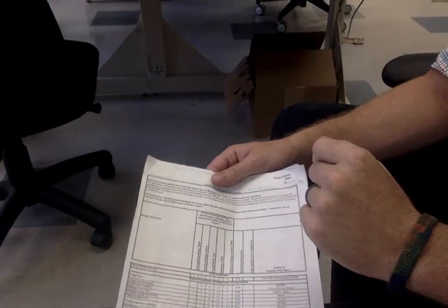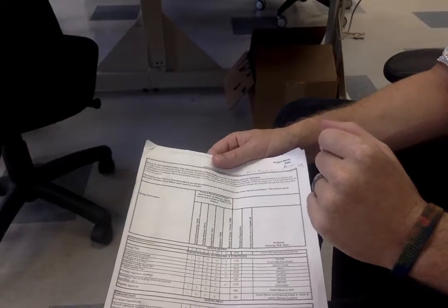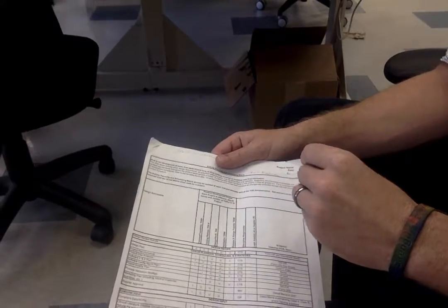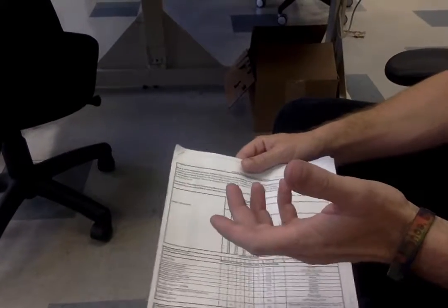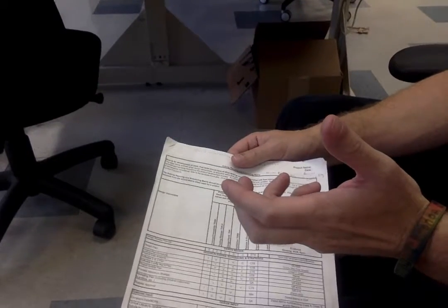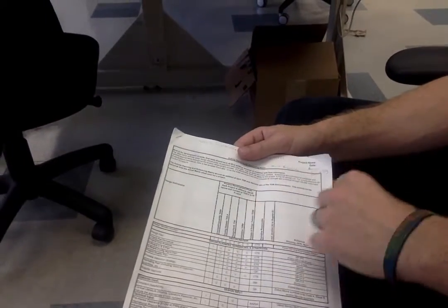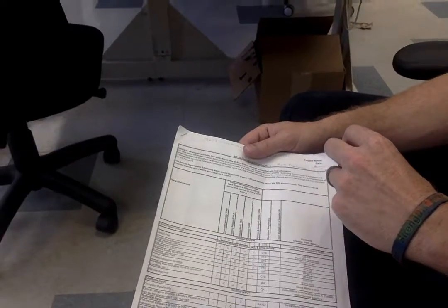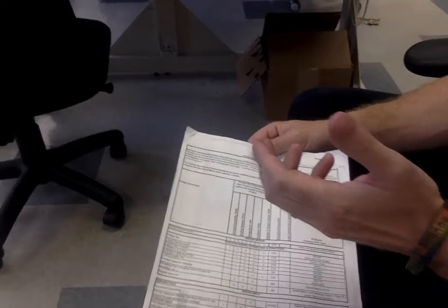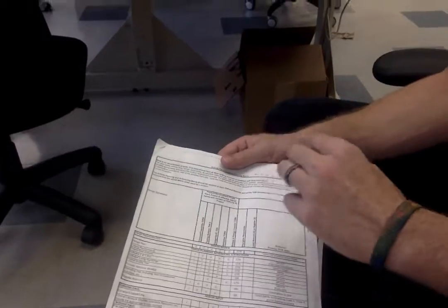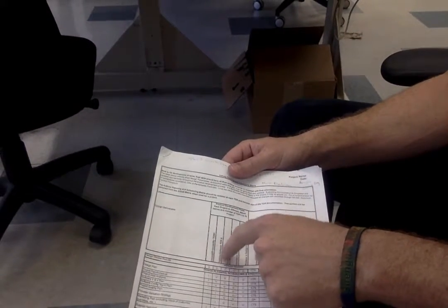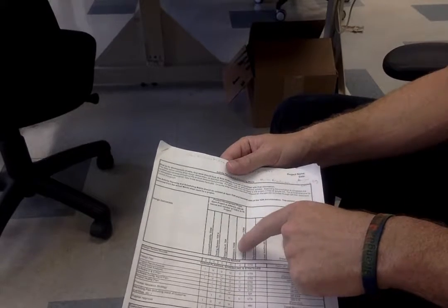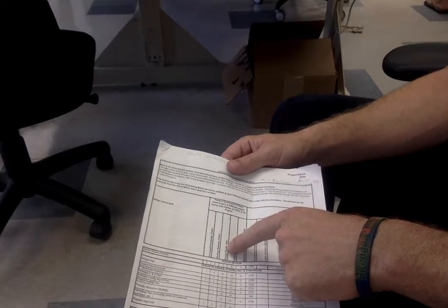Also in this stage, you would do things like a risk analysis and a cost analysis, and this is where you're starting to build up basically a flow chart of all the things that you're buying, how much they cost, but also how important they are for the successful use of your product. And if something is absolutely critical, what's the potential that it could fail and cause a problem or cause harm? You don't want any of that. So you're doing some testing, bench testing, and things like this. So verification is one step.